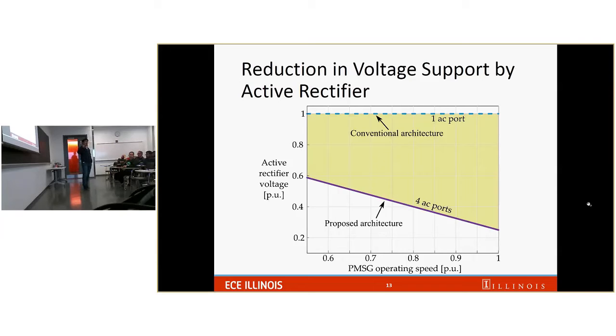But if we series connect this active rectifier with the passive one, at the rated speed, with 4 AC ports, meaning we have 3 passive rectifiers and 1 active rectifier, we calculate that it only needs to provide about 25% of the DC bus voltage. As the speed decreases, the back EMF of the generator decreases, and that leads to a decrease in the DC bus voltage provided by the passive rectifier. So in order to maintain the DC bus voltage at a constant value, the active rectifier has to increase its voltage, so the sum of the two still stays at 1 per unit.